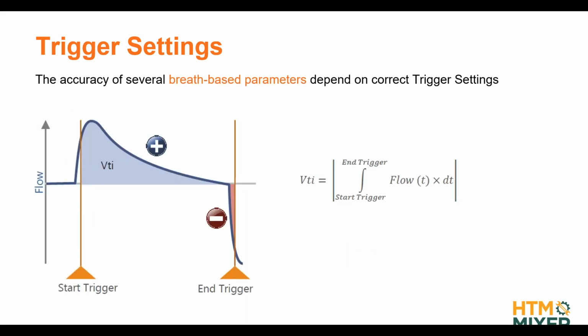Okay, so even if our analyzer is triggering, and that's the first thing we needed, if we have insufficient trigger settings, that's going to have an impact on the accuracy of our measurements. So ideally, we want our trigger settings as close as possible to reality, right? In this flow waveform here, you see it's 0 and then suddenly it starts increasing, then it goes back to 0, and then suddenly it goes negative. So exactly from here to here is our inspiration phase. There, ideally, we want to have the triggers of our gas flow analyzer.